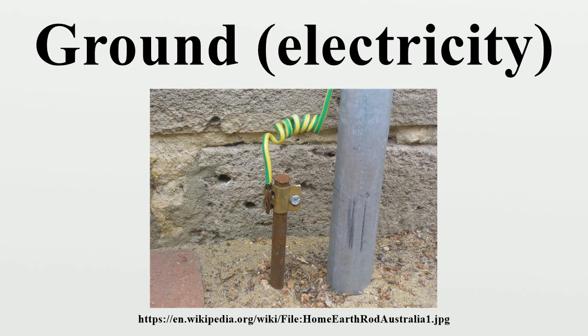Although no phase conductor is directly connected to ground, a specially constructed transformer blocks the power frequency current from flowing to earth, but allows any leakage or transient current to flow to ground. Low-resistance grounding systems use a neutral grounding resistor to limit the fault current to 25A or greater. Low-resistance grounding systems will have a time rating that indicates how long the resistor can carry the fault current before overheating. A ground fault protection relay must trip the breaker to protect the circuit before overheating of the resistor occurs.